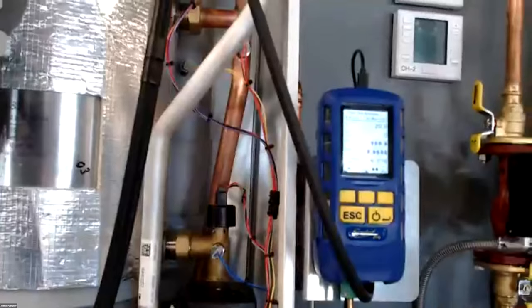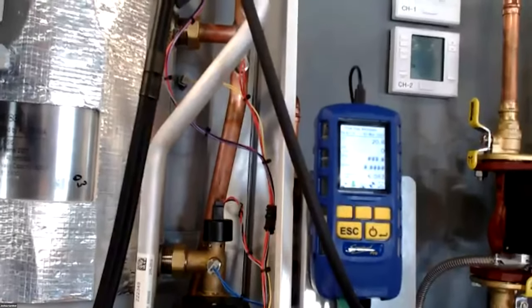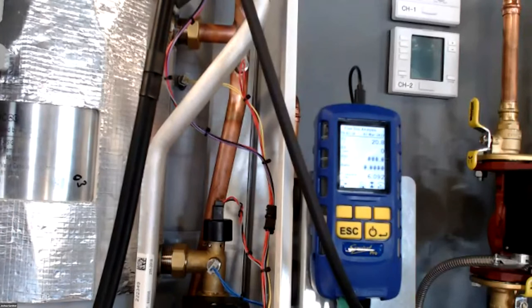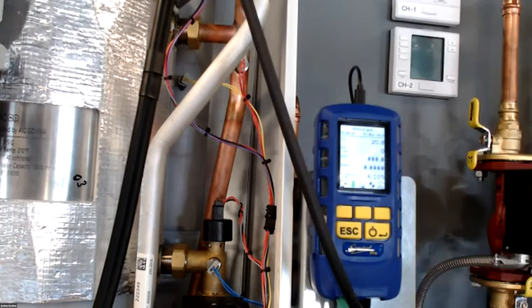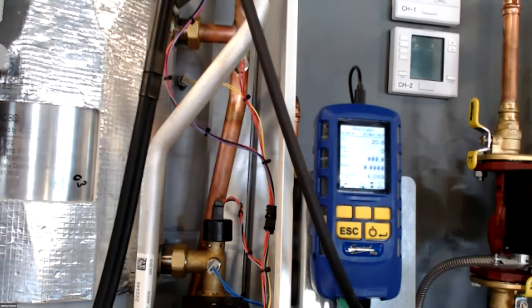That torching is caused when it's running really lean. So we'll have the flame kind of rolling in the burner, not getting out of the burner, and that's when that torching happens. On certain gas pressures and gas setups and venting, when everything's just in the right way, it can cause that. We have found it happen on some earlier models on propane with real lean mixes. And we had come out with a conversion kit that is updated with new fan speeds.